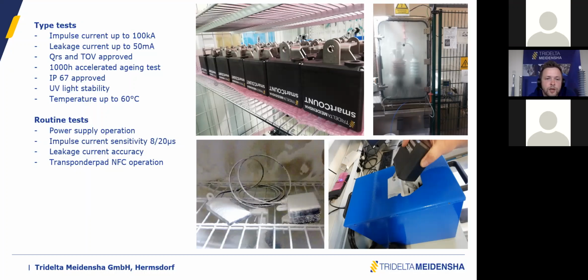And then we also run routine tests. For us, it's important to verify the quality of each single device we are delivering. There we verify the power supply operation. We verify the impulse current sensitivity for lightning currents. And we verify that the leakage current measurement is precise, and we test the transponder pad NFC interface to check that the communication is working. So this is a complete routine test to verify all the functions of the delivered devices, conducted on each single delivered device.